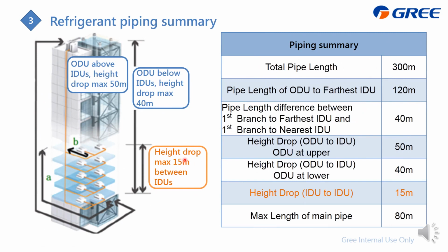And this is the refrigerant piping summary. For the refrigerant piping, the total length is 300 meters. From the outdoor unit to the furthest indoor unit is 120 meters. The height drop from the outdoor unit to the indoor unit is 50 and 40. And the height drop between indoor units is 15.